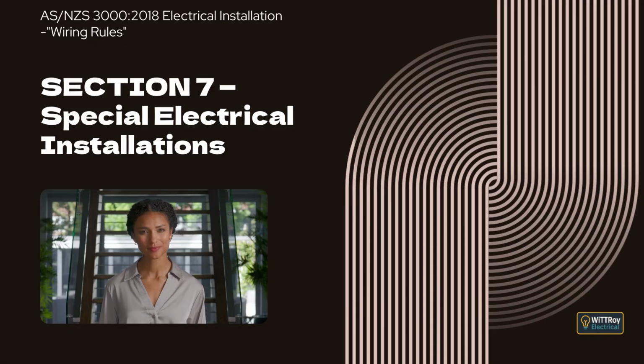Clause 7.5.4, Separation requirements for SELV and PELV circuits. This clause explains that live parts of SELV and PELV circuits must be electrically separated from each other and from higher voltage circuits. It explains that separation must be equivalent to that provided by a safety isolating transformer, and that conductors must be segregated from other circuits. It also explains that live parts must be arranged so that short-circuiting or arcing will not occur under normal service conditions. Clause 7.5.5, Arrangement of SELV circuits.